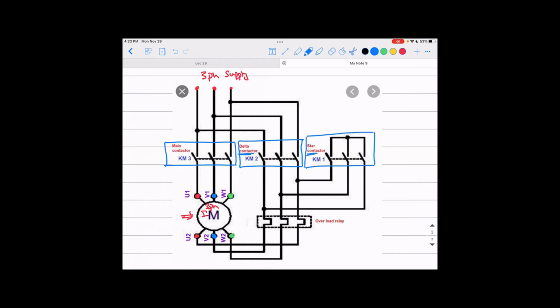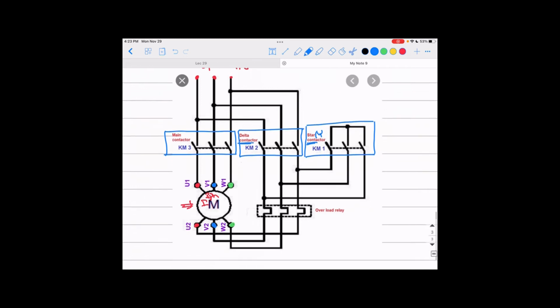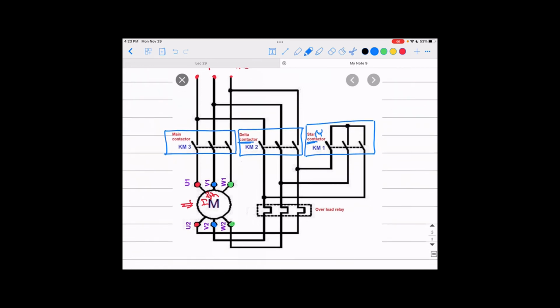So the delta contactor, from its name, if you close it while you're closing also the main contactor, the motor will be connected as delta. If you open this delta contactor and close the star contactor, or the Y contactor, because you know it's a star or Y, whatever you want to call it, you're basically connecting the motor as Y. It's simple as that. You can just go around this if you want to look at it here.